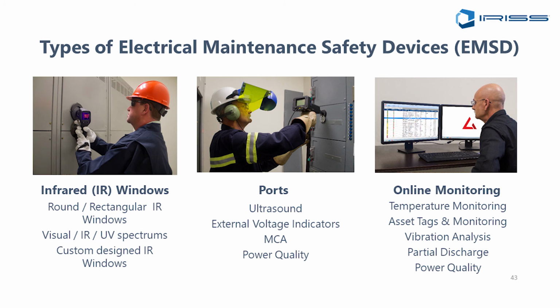Okay, so what are these things that fall into the substitution or safety by design thing? Essentially, it's any type of what we call an electrical maintenance safety device. It could be infrared windows, ports for listening for ultrasound, ports for connecting test voltage and current for power quality, for your motor current analysis, the MTAPs, they call them motor test access points. All of those are sort of things. And then lastly, the online monitoring piece as well.